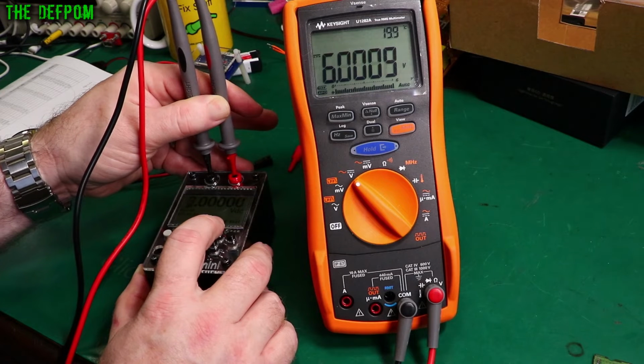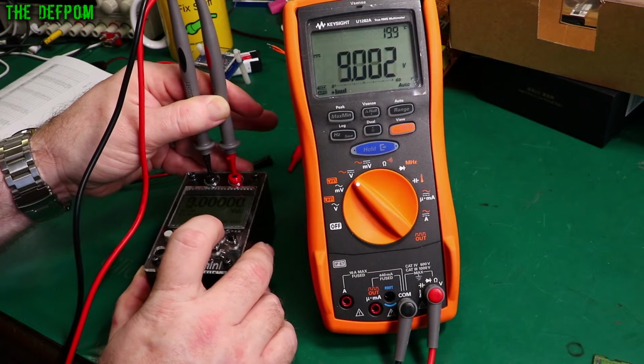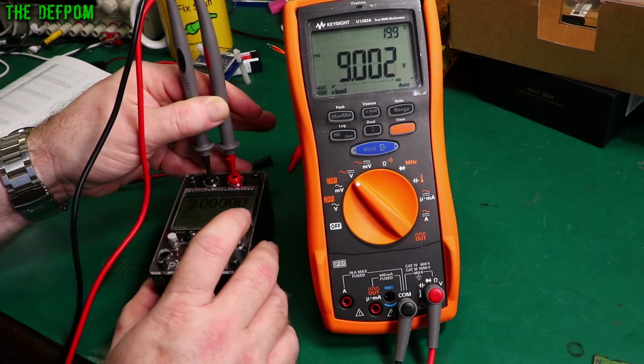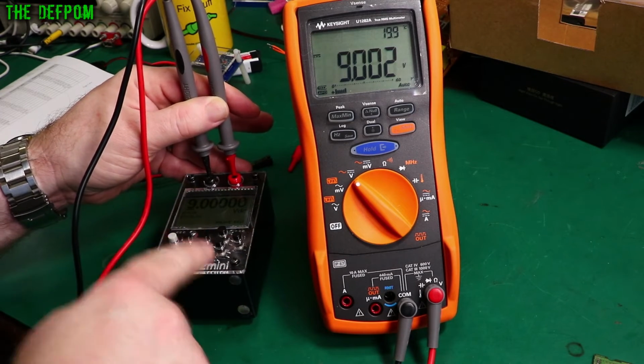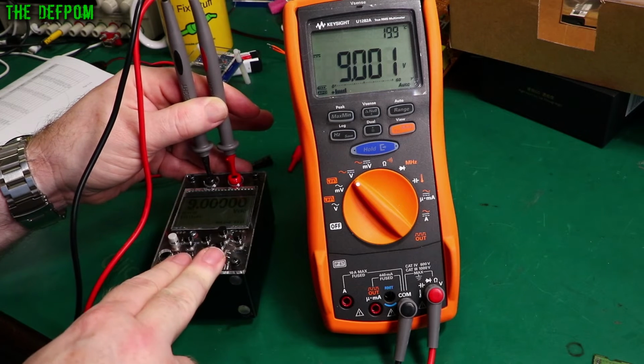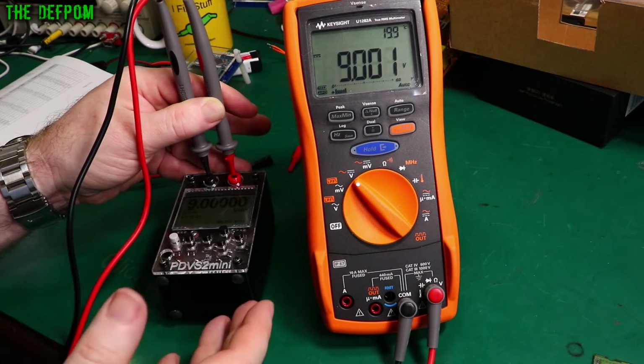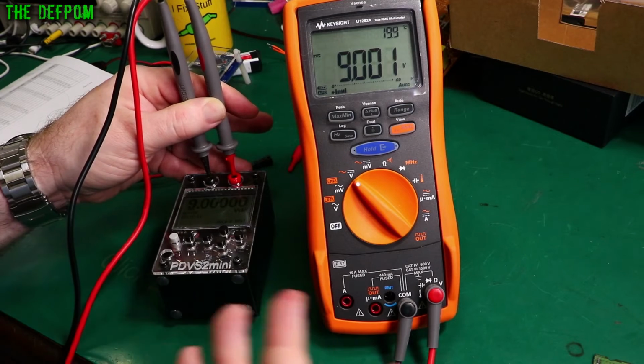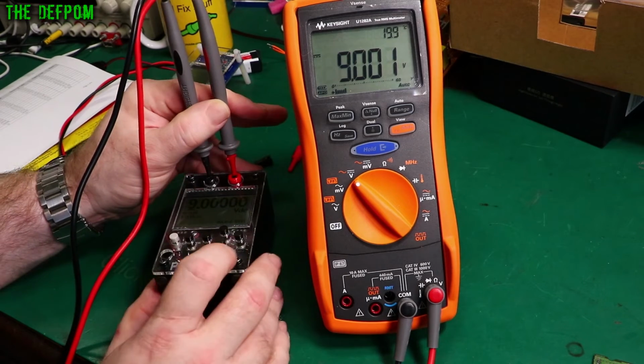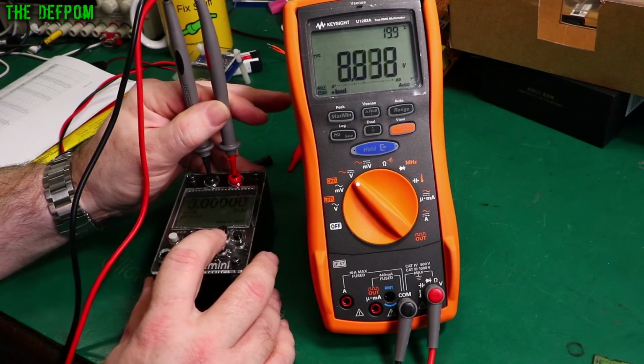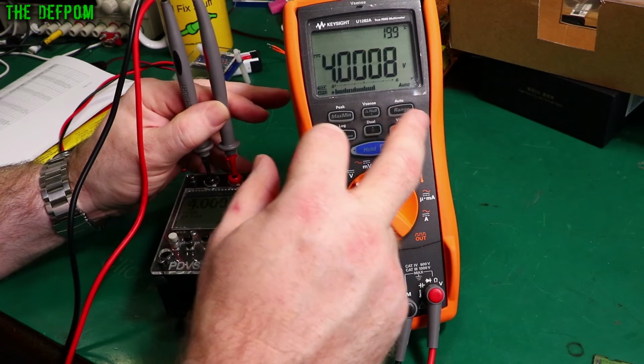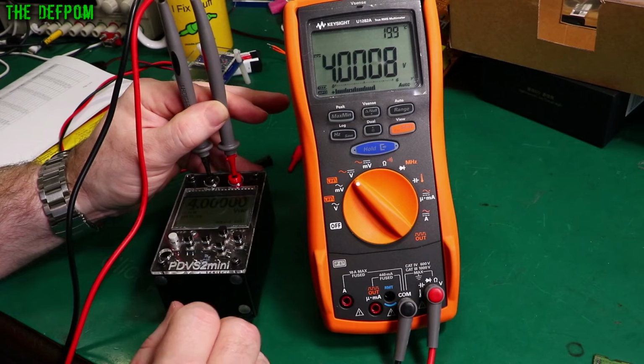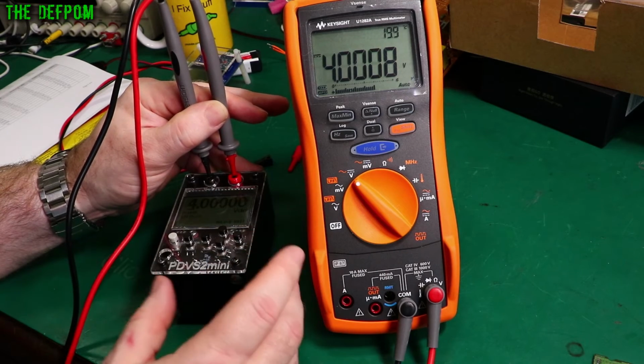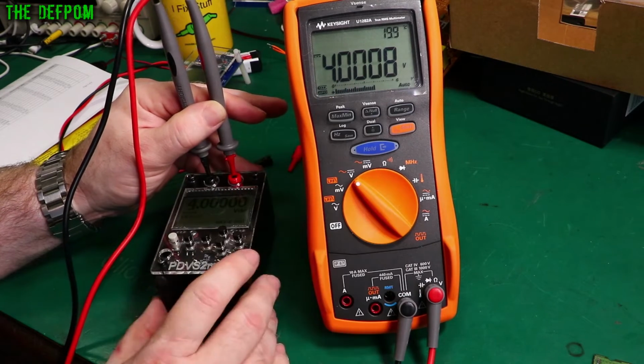Interesting, look at that error there. Which one's wrong? See, I trust this thing really well. I have a really high confidence level in this particular unit because it's always proven to be accurate, and in all the cross checks I've done, it's been really reliable. So this is actually making me a little suspicious about the calibration on this one. I mean, you can see I'm below temperature, right? I'm only 20 degrees right now. So maybe once it's been on for a bit longer, it will settle down. But I would have thought this would be a little bit closer than that.